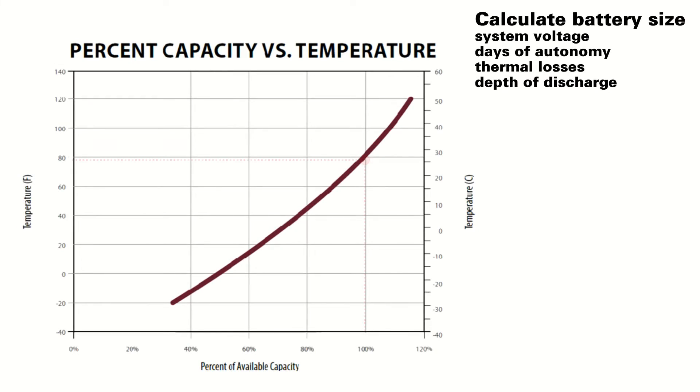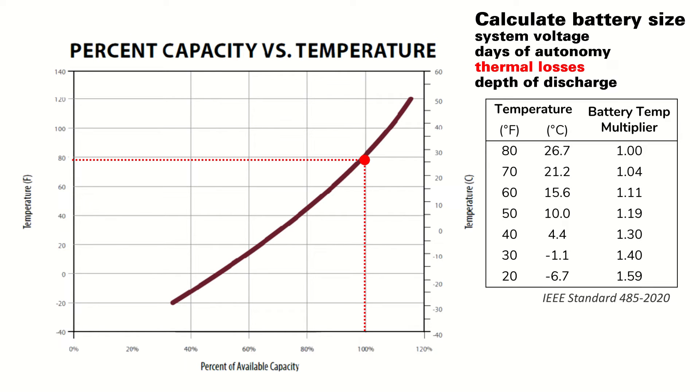You may need another power source like a generator if you choose fewer days of autonomy, but choosing more days increases system cost significantly. In this case we'll select three days of autonomy, which should provide sufficient reserve power for our application. While batteries are typically rated at 77°F (25°C), their capacity drops at lower temperatures. We account for this using a battery temperature compensation factor from the manufacturer's specification or IEEE standards. For a lead acid battery stored at an average winter temperature of 50°F, the temperature correction factor is 1.19.